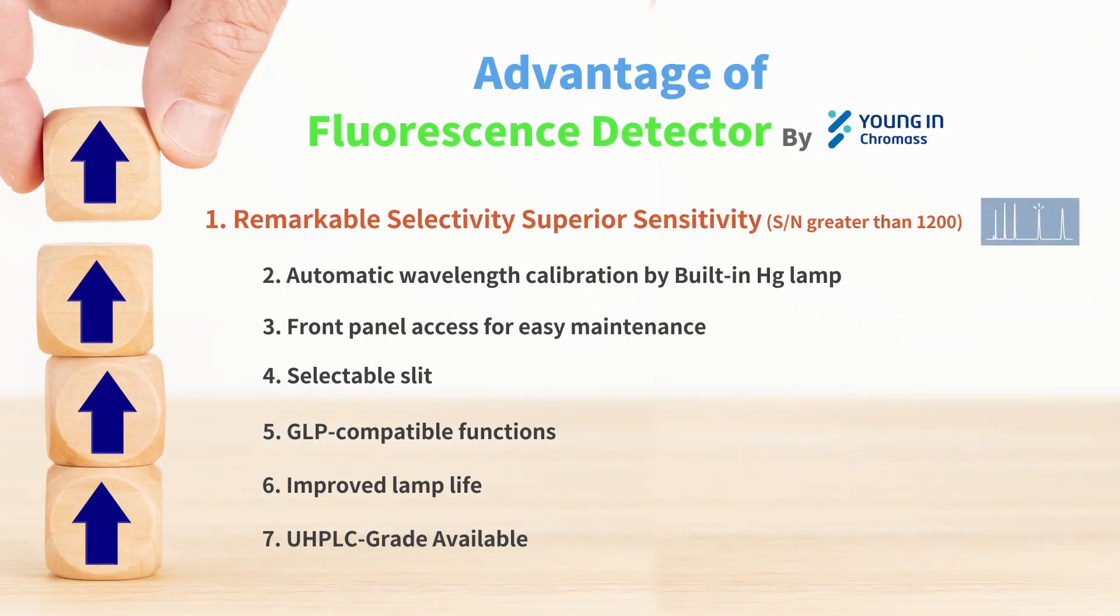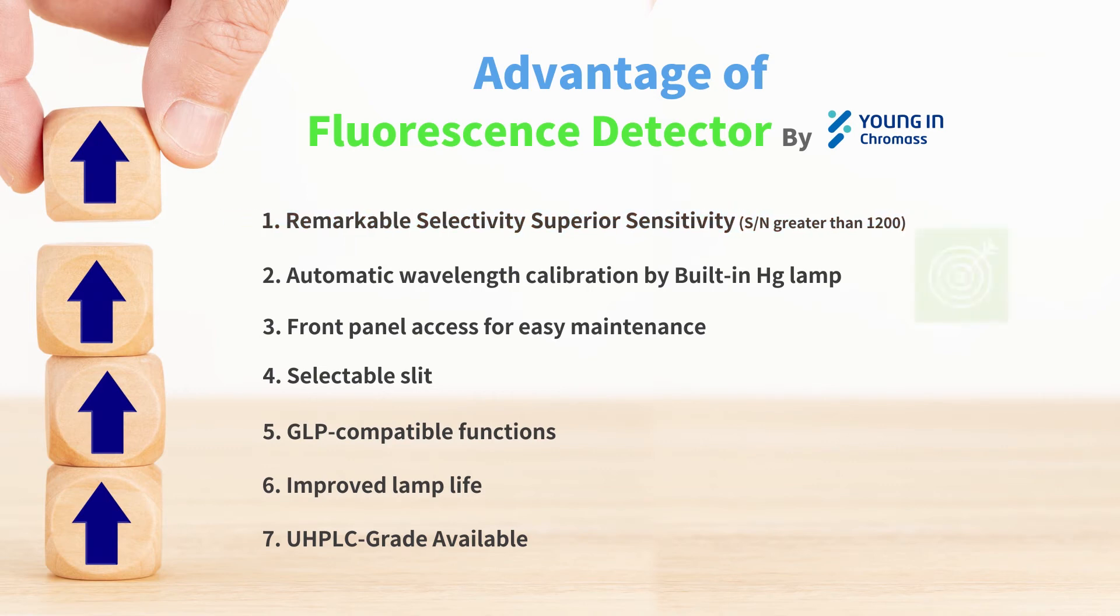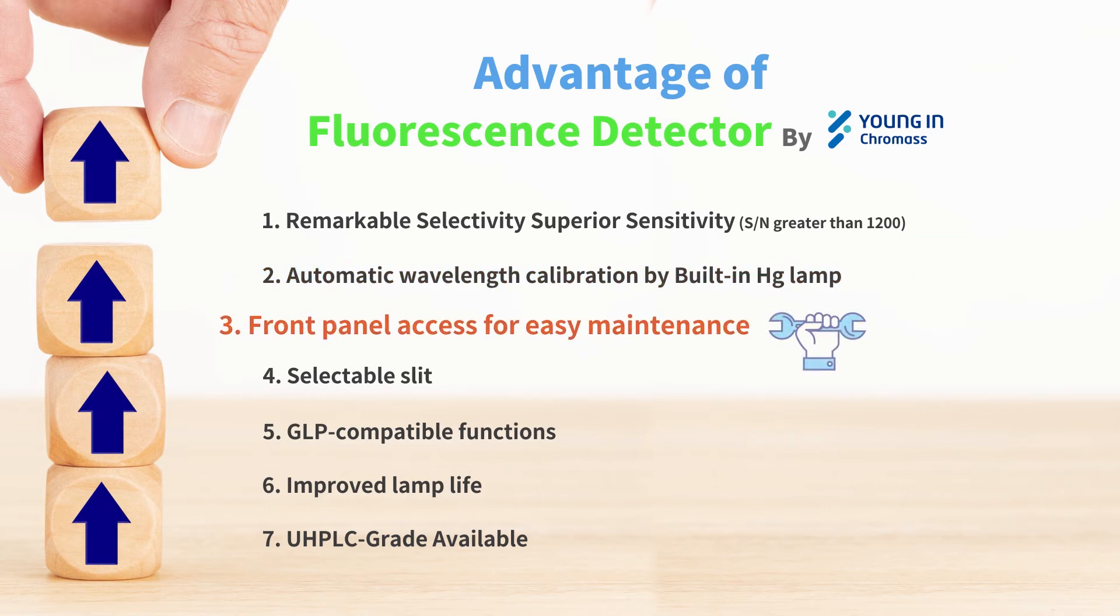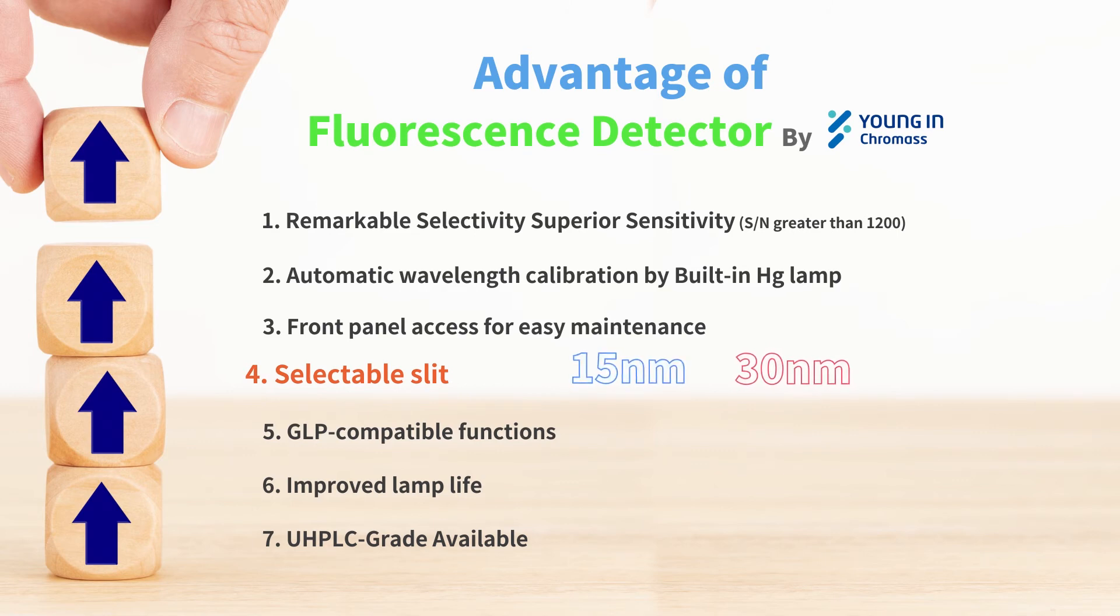Further to the selectivity and sensitivity as major advantages, our fluorescence detector provides automatic wavelength calibration through the built-in mercury lamp to ensure reliability. The major serviceable parts, such as positional adjustment of xenon lamp and flow cell replacement, are facilitated through front panel access for easy maintenance. The slit of the emission side monochromator is selectable between 15 nanometers and 30 nanometers for higher sensitivity.